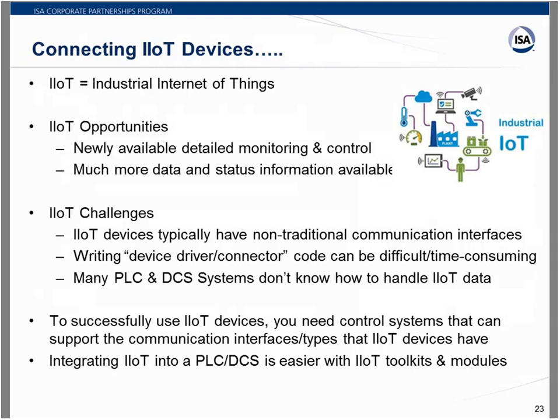However, if you look at a level transmitter implemented as Industrial Internet of Things, you could get a copy of its configuration, look at its performance over the last month, check the temperature of the transmitter, program individual alarms at the device level, run diagnostics, and look at a myriad of other features vendors are starting to provide in these devices, which is a lot more than a single data type.